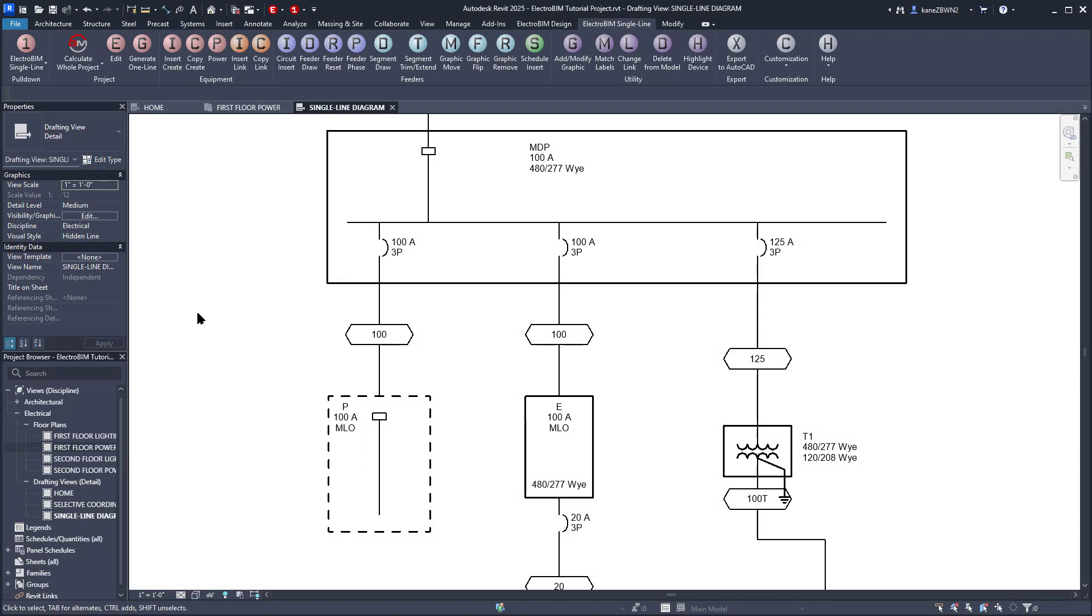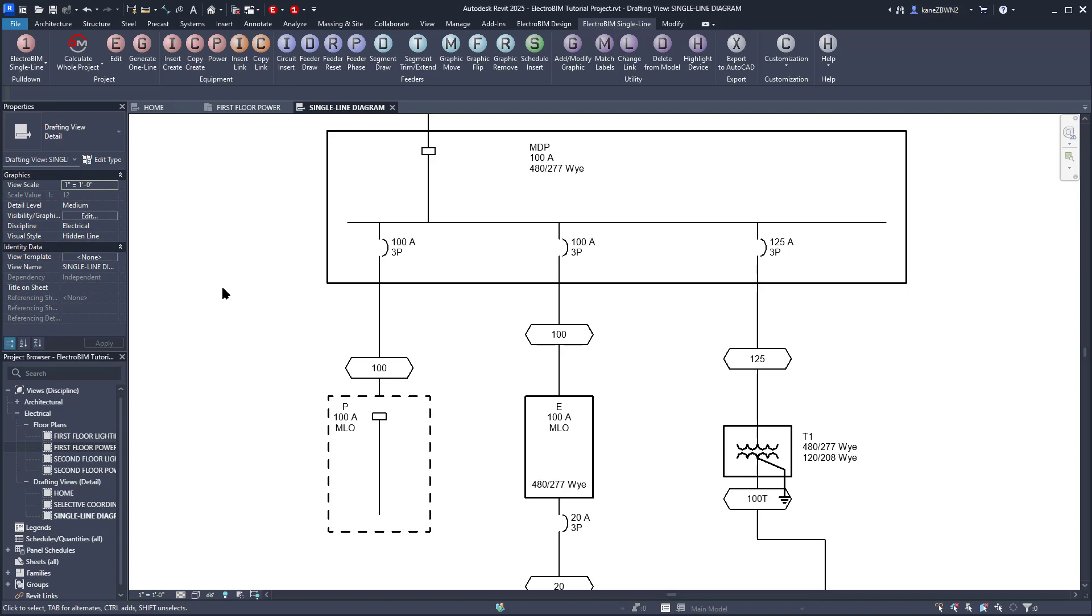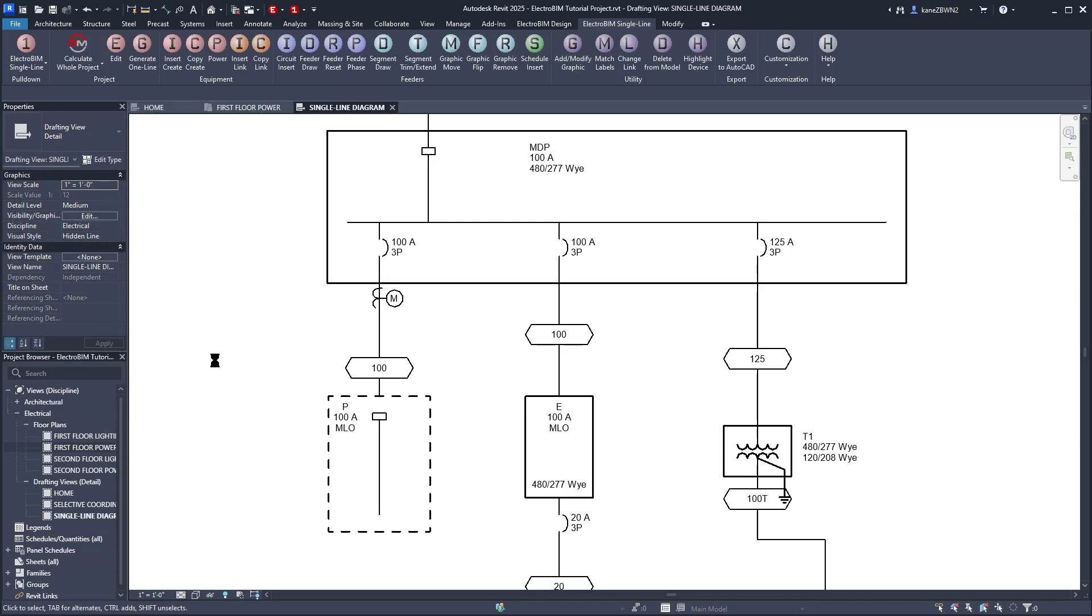As long as we're here, let's add a meter onto this feeder. First, we'll select the feeder ID, use the grip to make some room, then run the Add-Modify Graphic command again and select where we want the meter to go between these two graphics. Because this feeder segment already has a graphic on it, ElectroBIM will ask if we're trying to replace that graphic or add a new one. We're doing the latter. We'll set the Group to Meter, make sure it's using a regular meter and the Medium Solid line type. Press OK, and the graphic will be added in the location we specified.